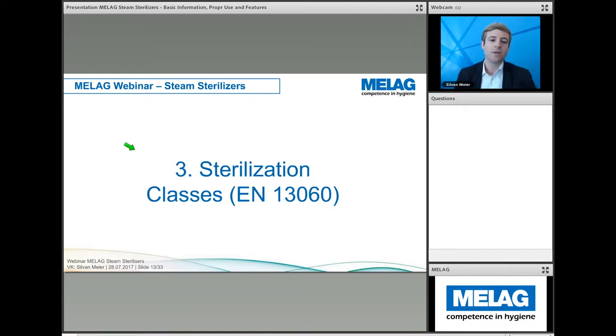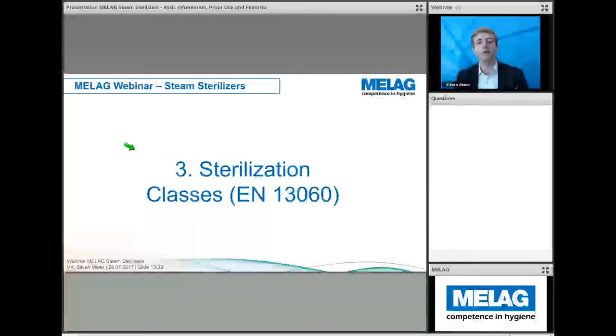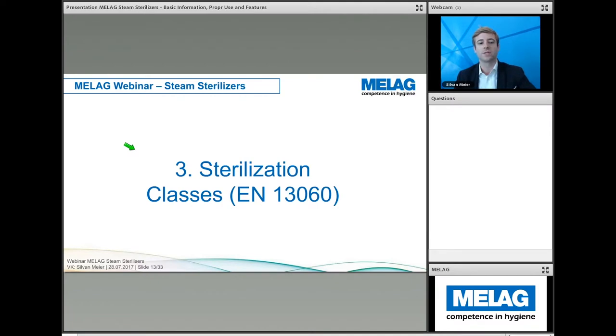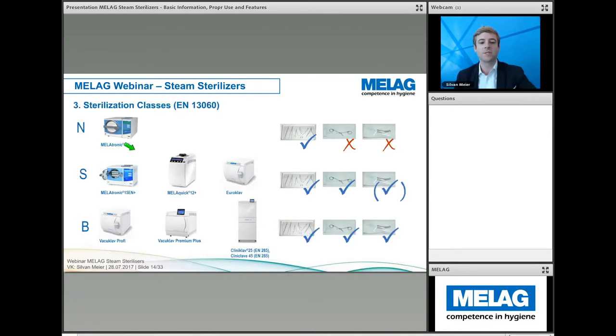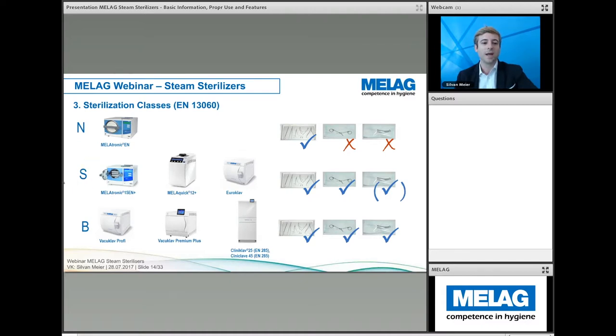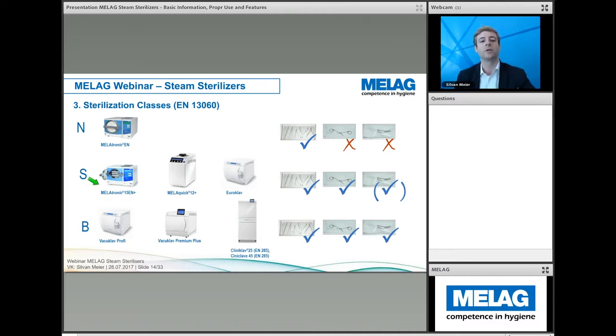All our products fulfill the highest quality standards, are reliable, and have a very long lifespan. There are different sterilization classes, and different autoclaves are needed for different instruments. In accordance with European norm EN 13060, there are three sterilization classes: Class N — the lowest; Class S — the middle; and Class B — the highest, for the highest standards.